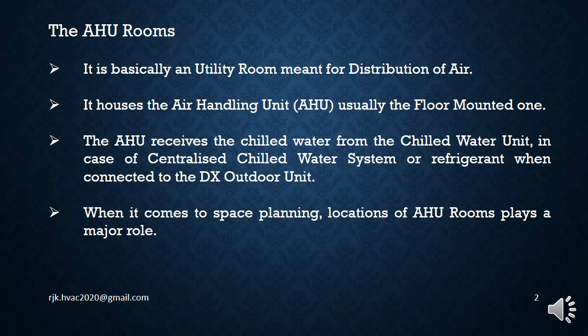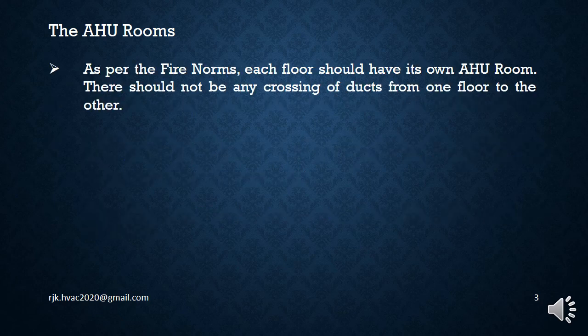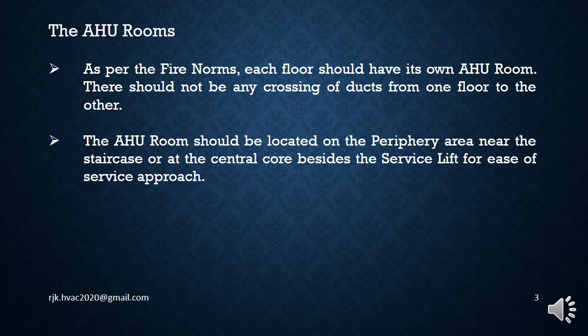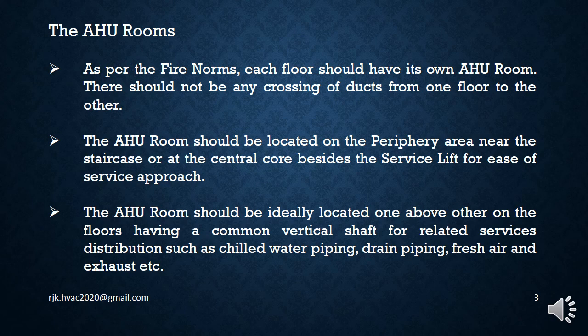When it comes to space planning, locations of AHU rooms play a major role. As per the fire norms, each floor should have its own AHU room. There should not be any crossing of ducts from one floor to the other. The AHU room should be located on the periphery area near the staircase, or at the central core beside the service lift for ease of service approach. The AHU room should ideally be located one above the other on the floors, having a common vertical shaft for related services distribution such as chilled water piping, drain piping, fresh air and exhaust etc.